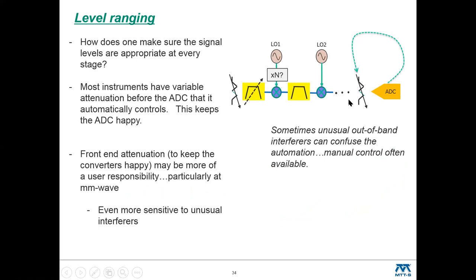There are cases where this can get confused if spurious energy gets through some of these spur prevention tactics. The A to D won't be able to figure it out—it has to figure out amplitude somehow. So there may be some way, sometimes when manual control is needed, and that's usually available at the front end. Oftentimes the user has some responsibility there, even in a full instrument, particularly if there are wideband interferers coming in that are not in the current measurement range.